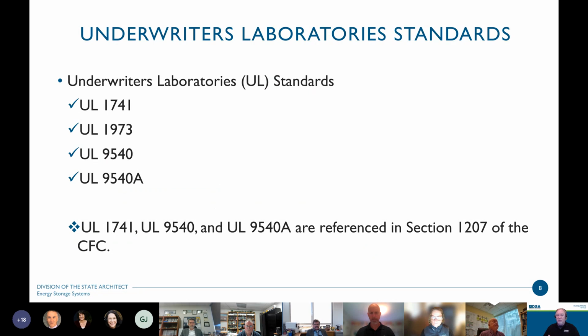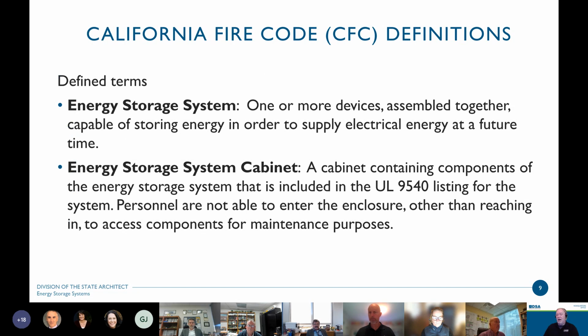Then of course we have the applicable UL standards: 1741 for equipment, 1973, and the two primary ones affecting our installations, 9540 and 9540A. To understand what we're talking about, energy storage systems as defined in the fire code constitute one or more devices assembled together capable of storing energy to supply electrical energy at a future time. There are also energy storage cabinets, which consist of a cabinet containing the components of an energy storage system included in the UL 9540 listing for that system.